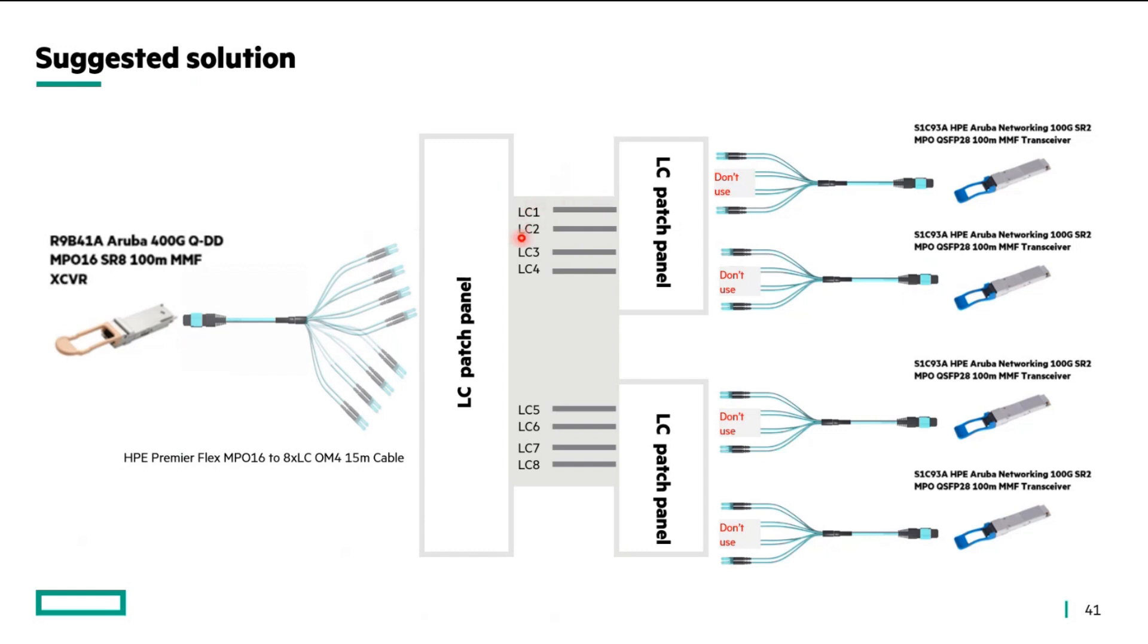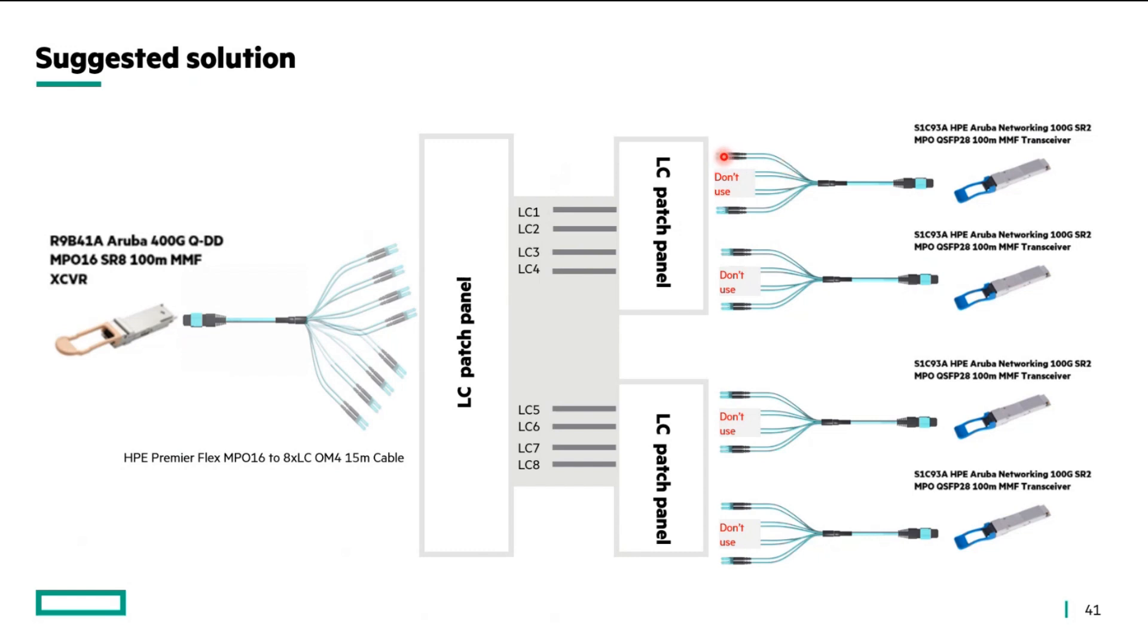Through the structured cabling infrastructure, it is then traveled to the other end of LC patch panels, where you took these out using MPO-12 to 4-LC split. Why this 4-split cable? Because you want to take 50 gig of these links that are coming in to your transceiver module. It is very crucial to understand this point, which I'll highlight in my next slide.